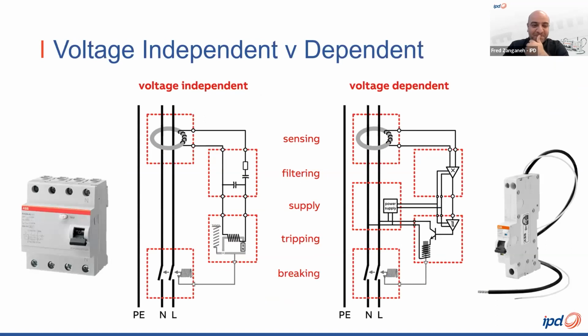Yeah. You know, Fred, in the technology of RCDs, we have two styles, the voltage independent and the voltage dependent. A voltage-independent RCD is sometimes known as an electromechanical RCD, and it uses the energy taken from the core balance toroid to power the tripping circuit of the RCD. The tripping relay used in these products is a highly sensitive, low-power relay specifically designed and manufactured for this particular purpose. And the other type, the voltage-dependent style, which can also be called an electronic RCD, uses power from the main circuit to operate the tripping operation of the RCD. This means the RCD needs a power supply in order to sense an imbalance.